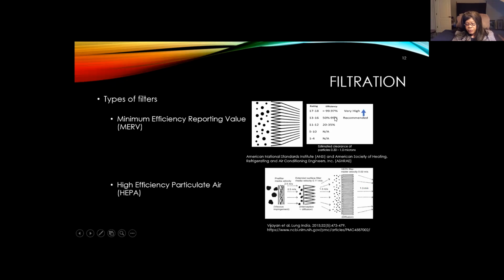ASHRAE, the American Society of Heating, Refrigerating, and Air Conditioning Engineers, recommends using MERV filters rated 13 or higher in our HVAC systems. The higher the filter rating, the better the filtration. It's also recommended that we use portable HEPA filters, high efficiency particulate air filters, to provide even greater air cleaning in certain areas.